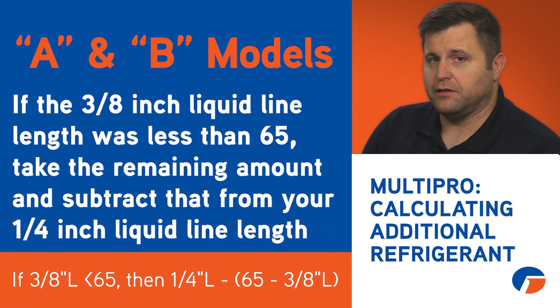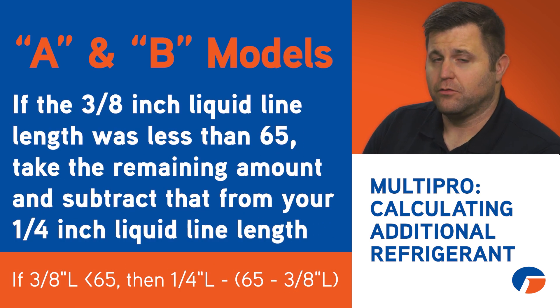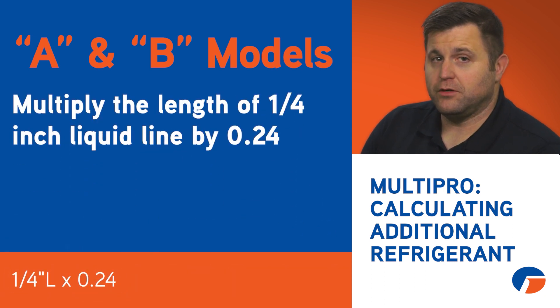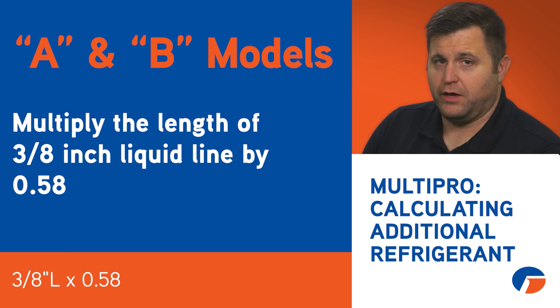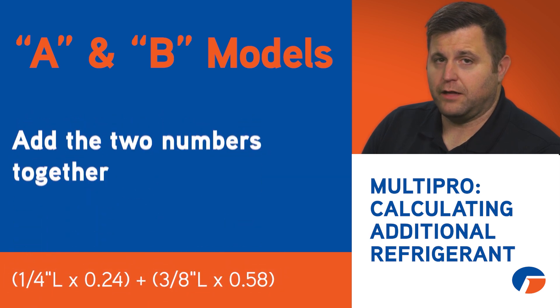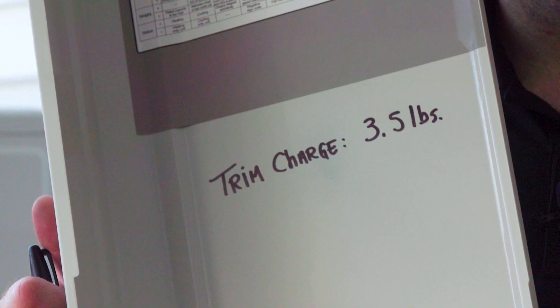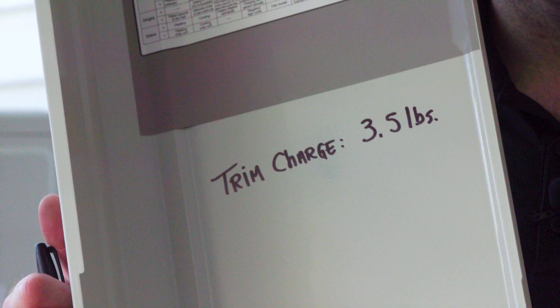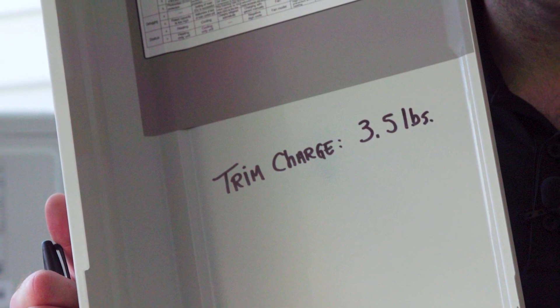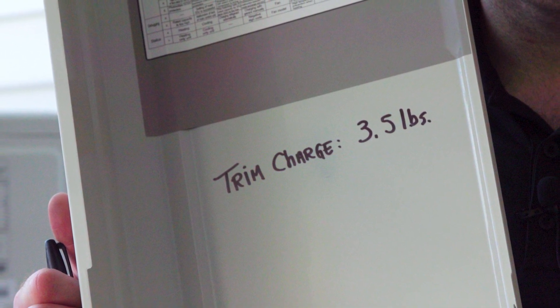You'll take the length of your three-eighths liquid line first and subtract 65 from this length. If your three-eighths liquid line length was less than 65, take the remaining amount and subtract that from your quarter-inch liquid line length. Then you'll multiply your length of quarter-inch by 0.24 and your length of three-eighths by 0.58 and add those two numbers together. Round up to the nearest ounce and write that number down on the inside of the access panel on the outdoor unit for future reference.